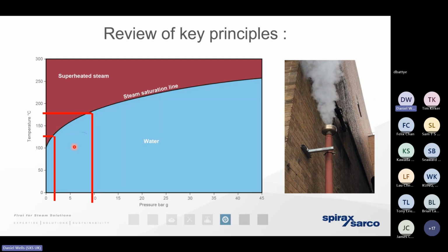So there are two things happening with those vents. We've got the steam that is passing across the trap and expanding. And we've got the condensate that is passing across the trap, depressurizing and expanding to an even greater factor, possibly as high as 1600 times. So of course we've got to vent that expansion away so we don't get damage imparted to the infrastructure. The problem is, whilst that steam is being vented into the sky, we're not recovering the condensate.